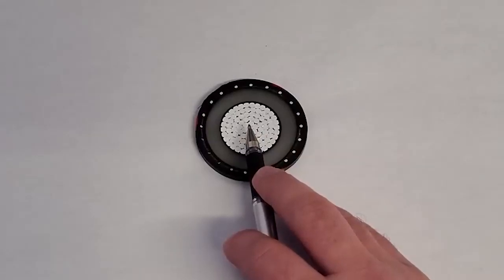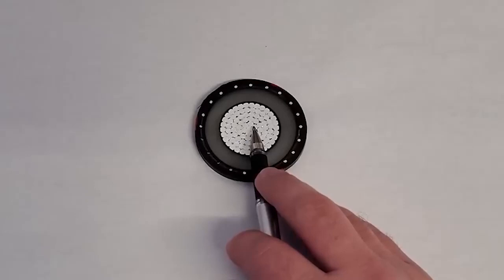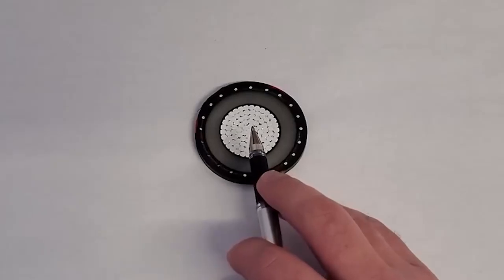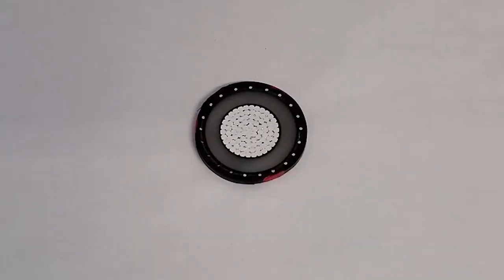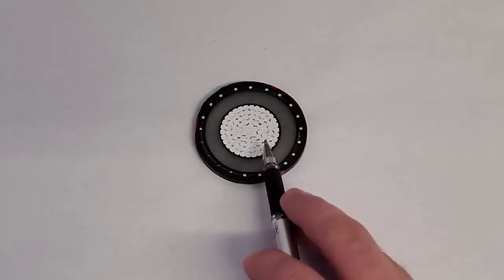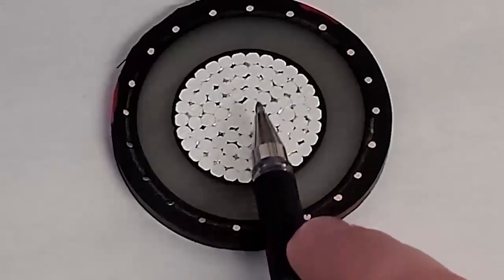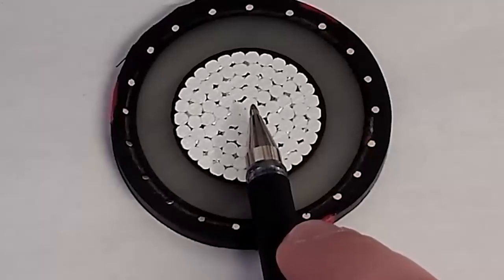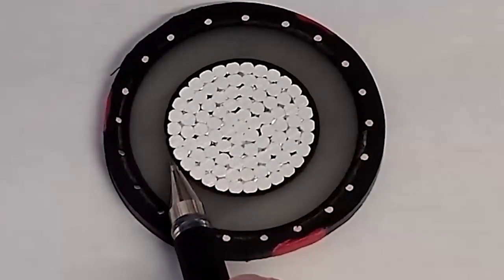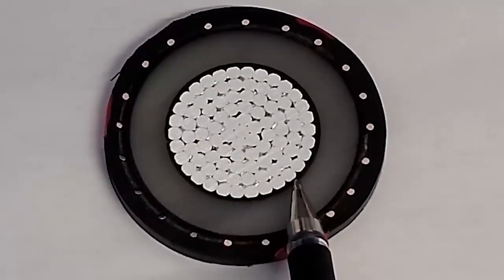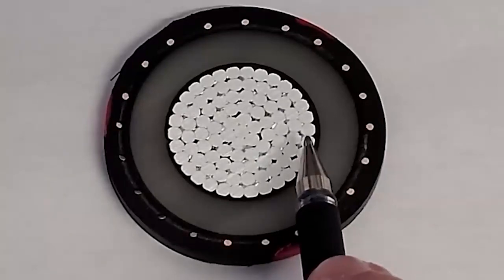But when you're installing things in conduit, there's no way you can have this be a solid piece of aluminum. There's no way you could install it. There's no way you could pull it through pipe. So really the compact and the compressed are the next best efficient way to go in the stranded configuration like this. This to me looks like it's compressed. It's definitely not compact because these are pretty round. I'm thinking that it's compressed because the outer ones aren't perfectly round. They do have a bit of squish to them.